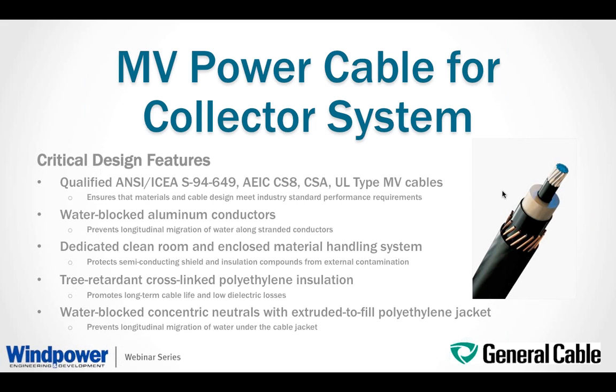All right, so here we're looking in more detail at the critical design features of the medium voltage power cable that is used in the collector system. First, I would say it is important to utilize a design that has been qualified to the ANSI/ICEA S-94-649 and AEIC CS8 standard and specification, and that the material is also CSA or UL approved. It also ensures that all the materials and cable design have been tested and certified to the applicable North American industry standard requirements.